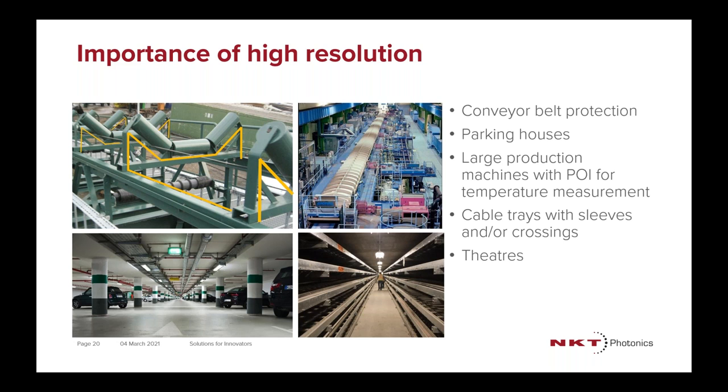If you install a linear heat detection cable straight over the cars, you need to detect a burning car, and that is why you need a high spatial resolution to get a fire signal very soon.